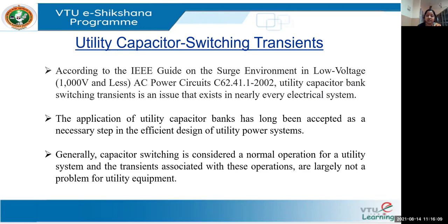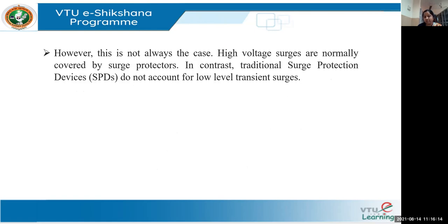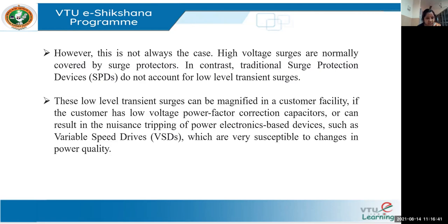Capacitor switching is largely seen at the utility equipment end. When we talk about surge arresters — especially traditional surge arresters — they are not going to be used much at this particular level of transient surges. So we need certain separate solutions, because those kinds of SPDs cannot be used for these kinds of surges.